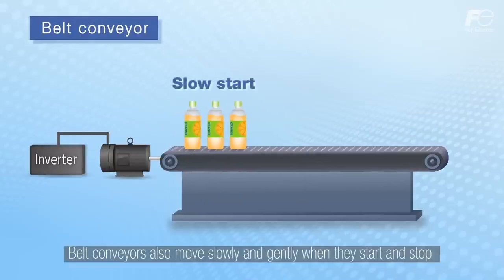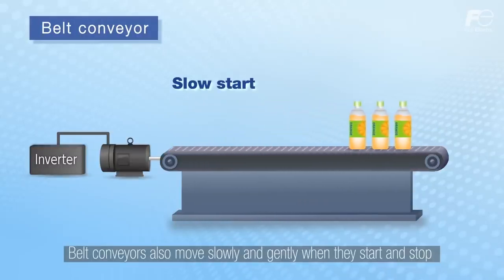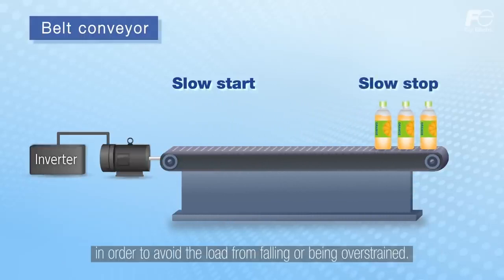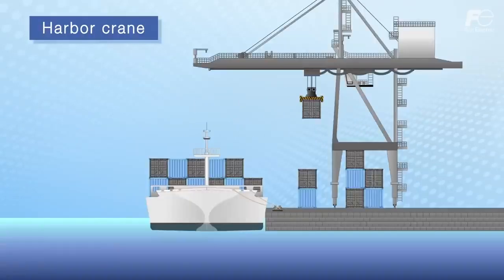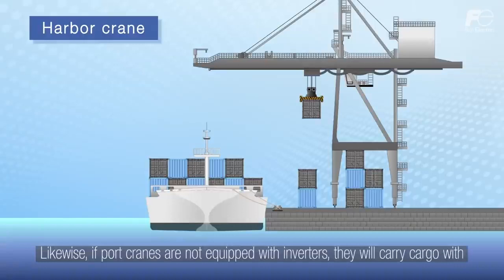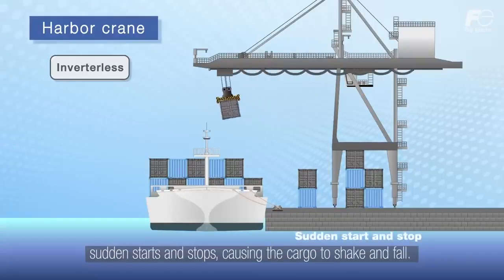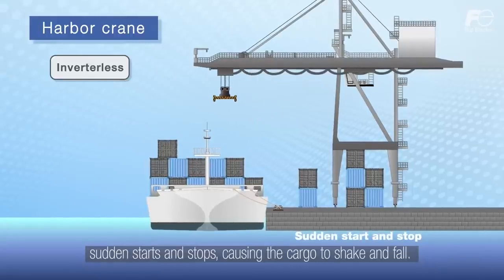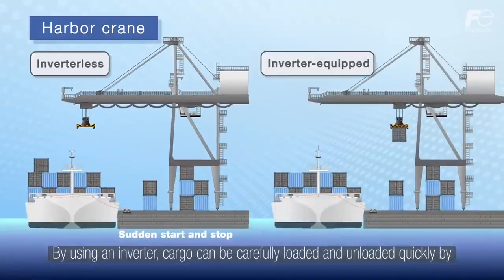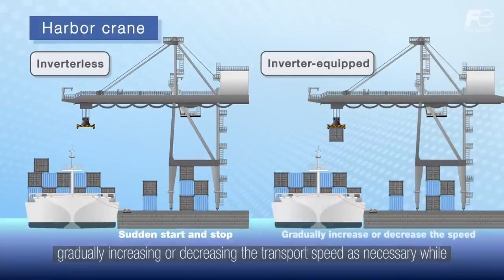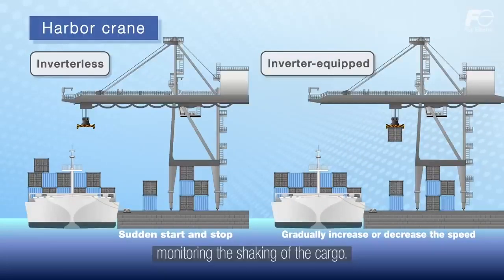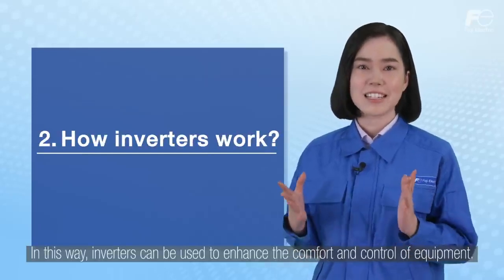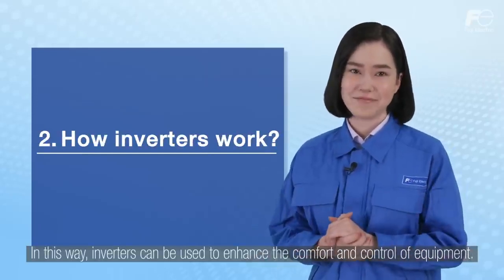Belt conveyors also move slowly and gently when they start and stop in order to avoid the load from falling or being overstrained. Likewise, if port cranes are not equipped with inverters, they will carry cargo with sudden starts and stops, causing the cargo to shake and fall. By using an inverter, cargo can be carefully loaded and unloaded quickly by gradually increasing or decreasing the transport speed as necessary while monitoring the shaking of the cargo. In this way, inverters can be used to enhance the comfort and control of equipment.